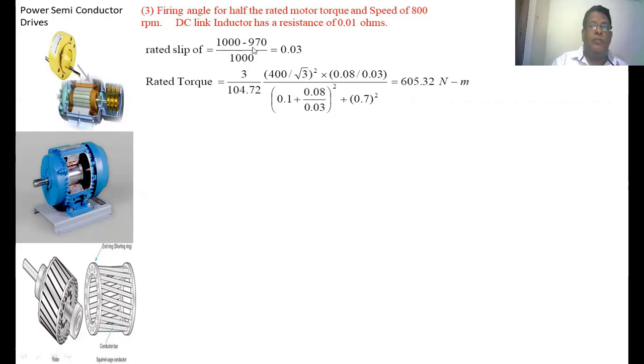Slip at full load = (1000 - 970)/1000 = 0.03. The full load torque, or rated torque = (3/ωs)·V²·(Rr'/S)/[(Rs + Rr'/S)² + (Xs + Xr')²]. Substituting all values, we get the rated torque = 605.32 N-m.